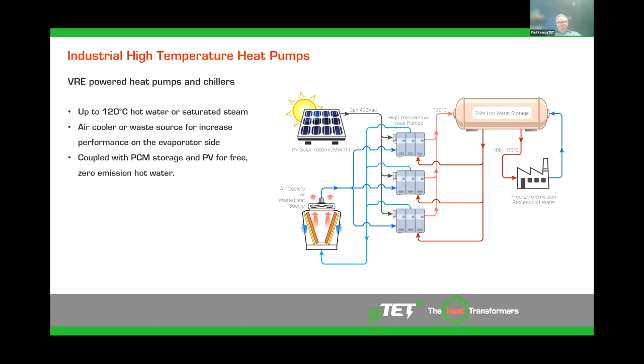As Jared says, and we've seen a number of times through A2EP, heat pumps provide a very effective means of producing thermal energy and supporting electrification. Operating on the Carnot cycle, heat pumps can move thermal energy with a COP of at least 2 on a lift at over 90 degrees up to a COP of at least 5 on a lift below 20 degrees. This means that heat pumps are excellent for leveraging low temperature waste thermal heat into more useful high temperature streams. gTET currently has heat pumps delivering up to 120 degree hot water, with versions exceeding 150 degree hot water currently in development. The ability for heat pumps to efficiently modulate and turn down to match consumer heat loads results in a much greater energy efficiency and lower emissions compared to more traditional technologies, including gas boilers, dryers, or burners.